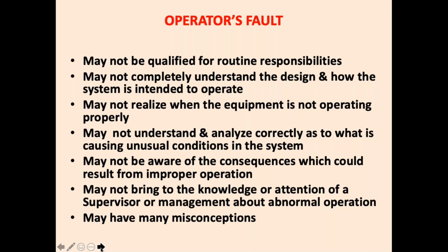So there may be many misconceptions that a lot of people have, which I have seen, especially on ammonia plants. 99% of people close the suction and discharge valves when they stop the plant and open the compressor suction. I said, why are you closing and opening the valves? They say, "This is the standard practice in ammonia plants, we close the compressor valve." I said, what is the reason? Do you do it in a Freon plant? When a Freon plant stops, do you shut off all the valves? They say, "No, it is not needed there, it is needed in ammonia." Why is it needed in ammonia? There is no answer. Now we have installed plants with 23, 24 compressors in a machine room, and you cannot close all the valves when the plant stops working.